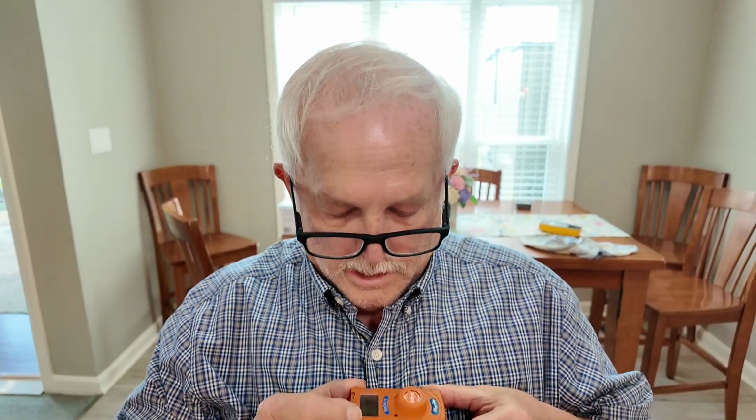One item I want to make you fully aware of: during a combustion safety test, you should be monitoring your carbon monoxide detector every time you go down to the water heater. The video camera didn't pick me up, but I wear mine on the shirt or on a pocket on the shirt, and I constantly look at it every time I walk down by the water heater. So that's a reminder for you every time, because it says continuously monitored CO, ambient CO in the combustion appliance zone.